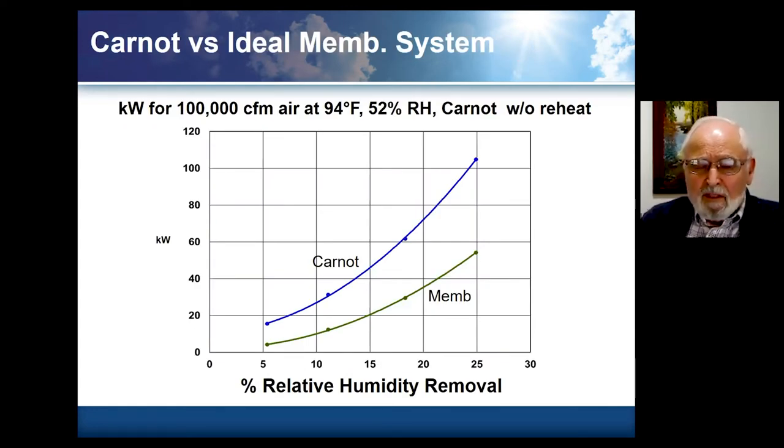To give a quick comparison with condensation processes: if we had a Carnot system taking air at 94 degrees Fahrenheit, 52 percent RH, and removing anywhere from five to 25 percent relative humidity, the Carnot system at five percent removal would basically require about 15 kilowatts. A membrane system doing the same thing would require about four kilowatts. As we remove more moisture the membrane advantage ratio becomes less, but the kilowatt difference becomes larger — at 25 percent removal, we're looking at something like 50 kilowatts for the membrane and a little over 100 kilowatts for the Carnot system.